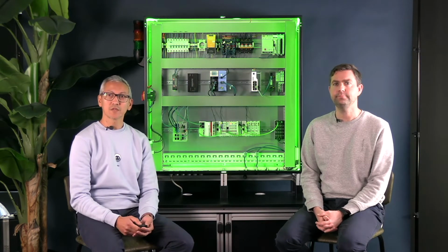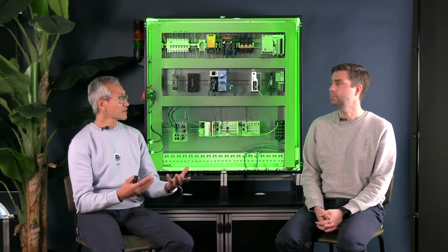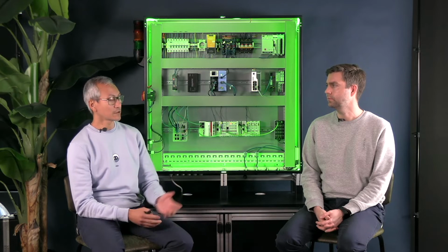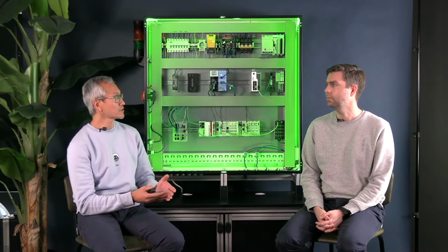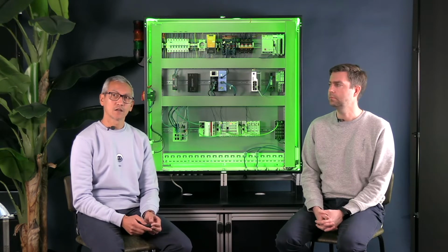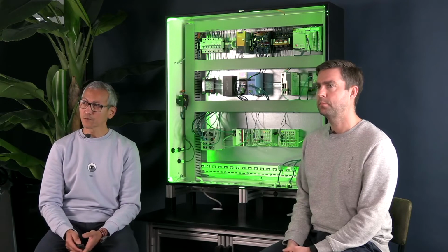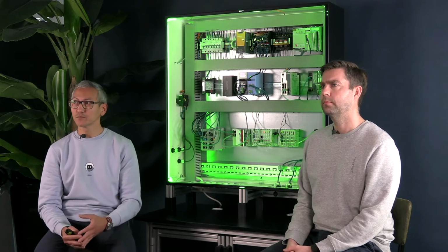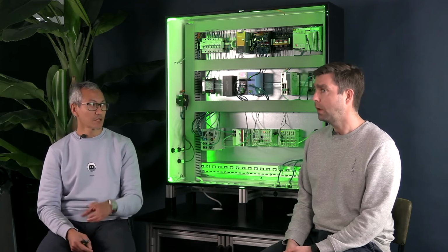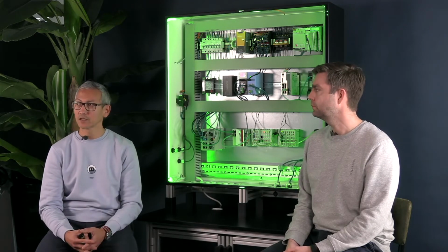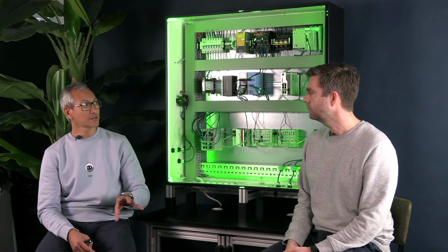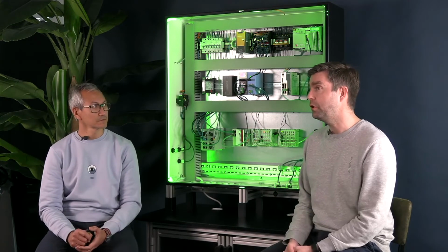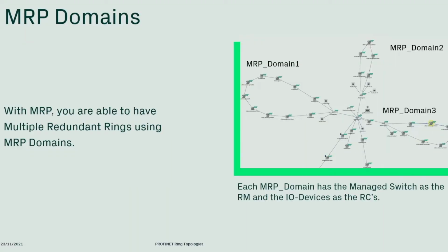Okay. So, knowing that, now you can see that ring topologies for redundancy are very easy. Mm-hmm. But you need to think about what happens if you are using a ring topology, especially in the form of redundancy in a ring. So, first of all, we can use multiple rings in one big network. And because we know messages can go everywhere in a network, but if we define our rings as domains, all the information stays within the ring. And in a scenario like that, would you monitor and troubleshoot the ring individually by the individual domain, or would you look at the entire network as one?